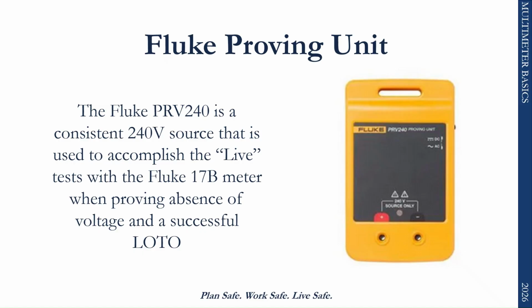The Fluke PRV240 proving unit is used to confirm that your meter is functioning correctly. This device provides a known voltage source, typically around 240 volts, which allows you to test the meter and confirm that it's reading accurately. This step is essential because if the meter fails or a test lead is damaged, it could incorrectly indicate that a circuit is de-energized when it is not. By using the proving unit before and after testing, we verify that the meter was working correctly during the entire testing process. This is a key part of the live-dead-live procedure, which we'll talk about in more detail in a moment.